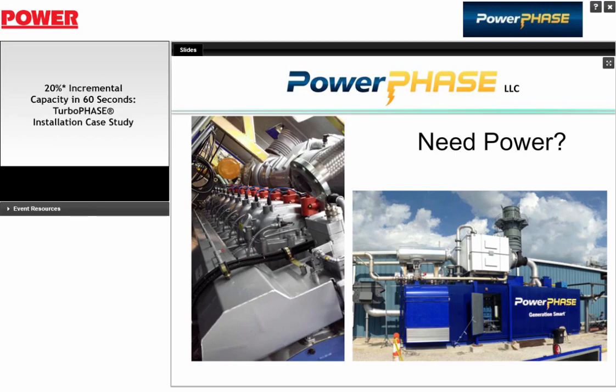And we're working with a number of customers in areas like California, for example, that have a 2 ppm requirement out the stack, and we can easily maintain the 2 ppm by putting our exhaust into the gas turbine stream and through the SCR of the gas turbine, and maintain the 2 ppm out the stack. And as well, when you look at how you operate the plant, since this incremental power is so much more fuel and emissions friendly than a duct burner, if you operate duct burners at all, you'll see a net reduction in emissions output from your plant. So that's kind of a high-level summary. The diesel system, most places where you could burn diesel, they're not that particular about emissions, but there is an SCR system that we offer for the diesel system if you want.